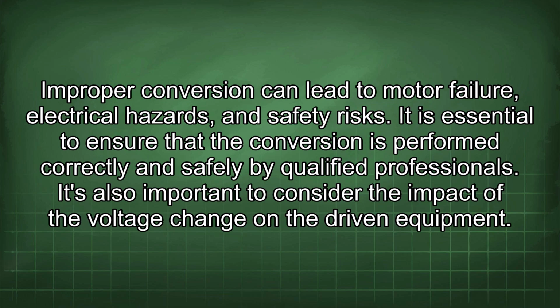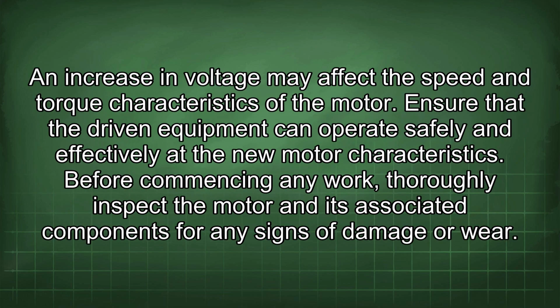It's also important to consider the impact of the voltage change on the driven equipment. An increase in voltage may affect the speed and torque characteristics of the motor. Ensure that the driven equipment can operate safely and effectively at the new motor characteristics.